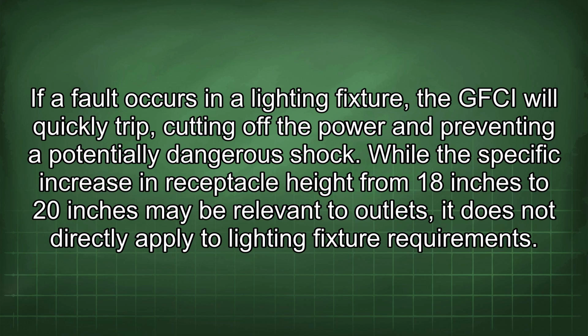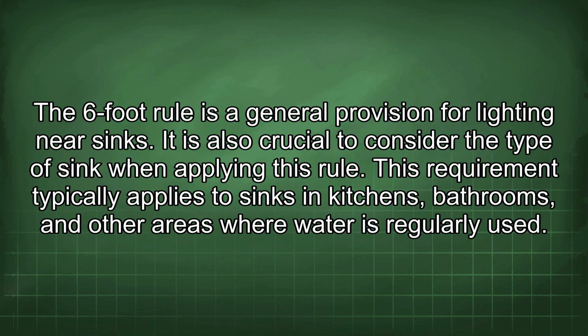potentially dangerous shock. While the specific increase in receptacle height from 18 inches to 20 inches may be relevant to outlets, it does not directly apply to lighting fixture requirements. The 6-foot rule is a general provision for lighting near sinks. It is also crucial to consider the type of sink when applying this rule. This requirement typically applies to sinks in kitchens, bathrooms, and other areas where water is regularly used.